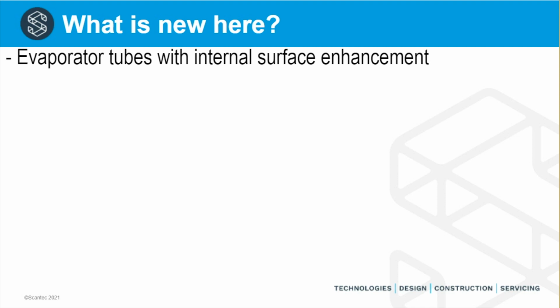It is possible to make the plant work with smooth tubes without internal surface enhancement, but I would recommend against using material with a relatively poor thermal conductivity. It is possible to make it work with galvanized steel evaporators and smooth internal surfaces, and it is very possible to make the evaporator work with smooth aluminium tubes. Aluminium has a thermal conductivity that is approximately 10 times higher than stainless steel, and that is an important factor. This was established in 2008 by a gentleman by the name Dermot Cotter, who now works for Star Refrigeration in Glasgow. He did his PhD and was able to record the behaviour of boiling ammonia as a function of the thermal conductivity of the core tube material.